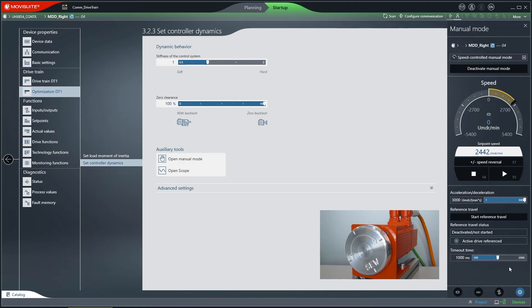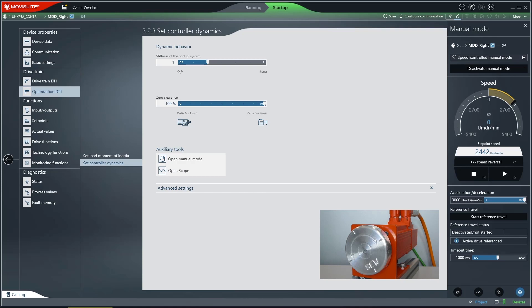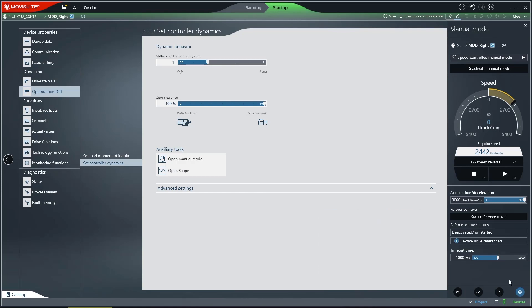You must perform a reference travel before you can activate position-related manual mode. Pressing the Start Reference Travel button begins the process. Now that the drive is referenced, it can now move to setpoint positions.